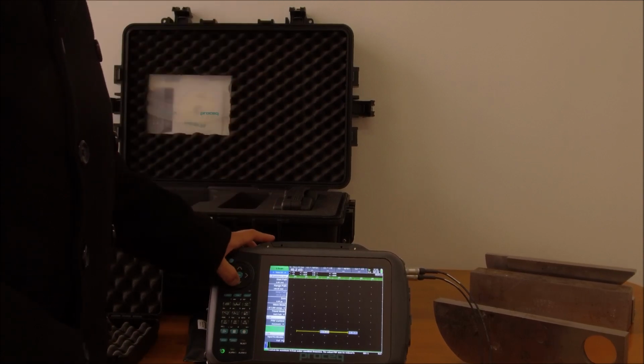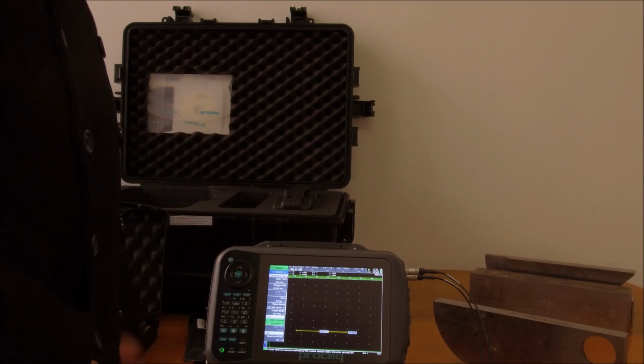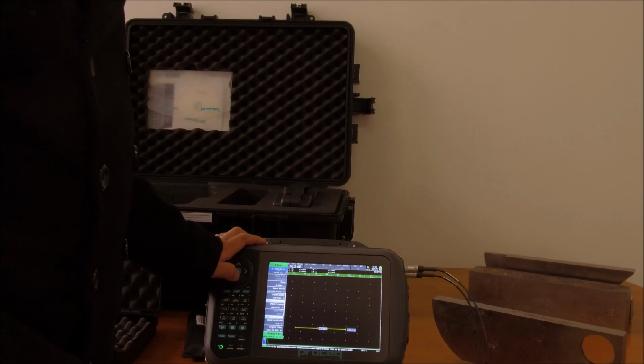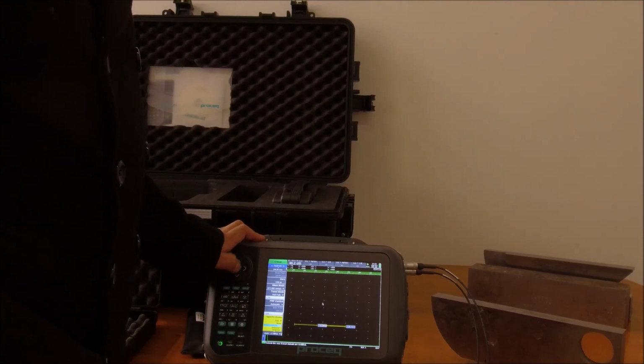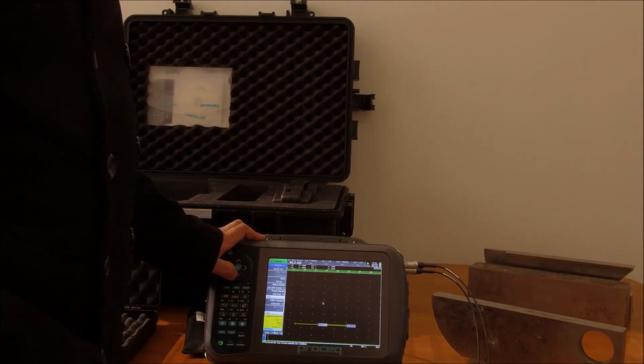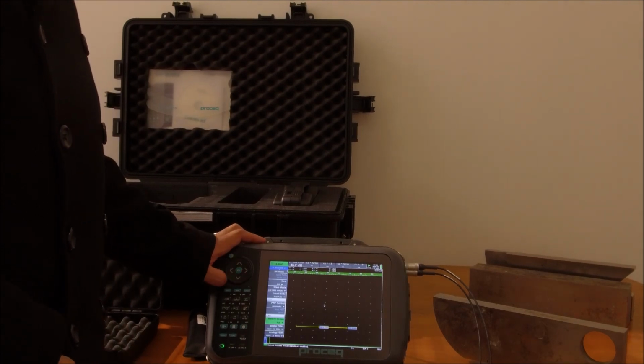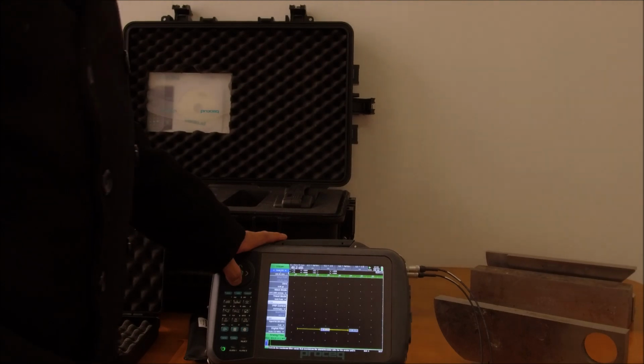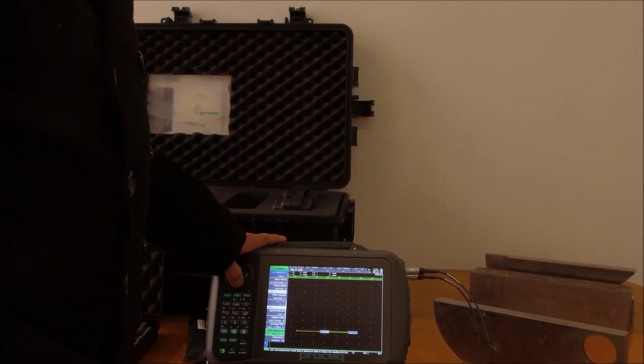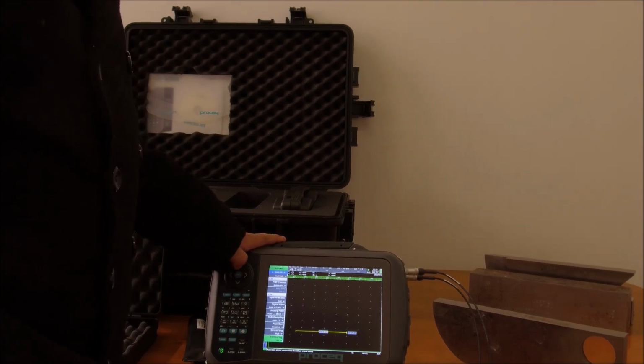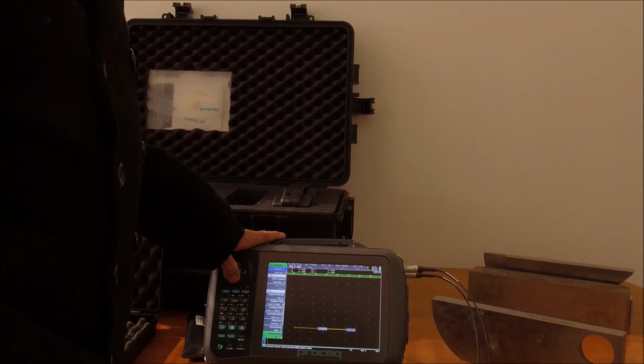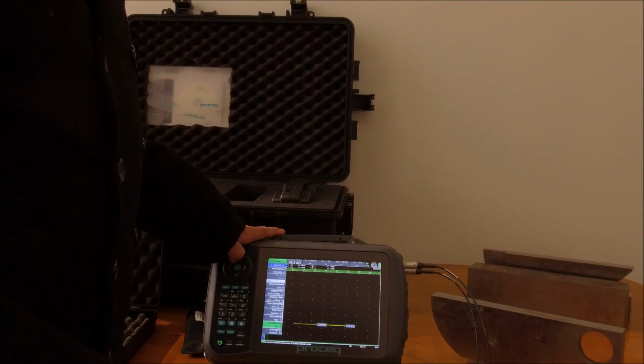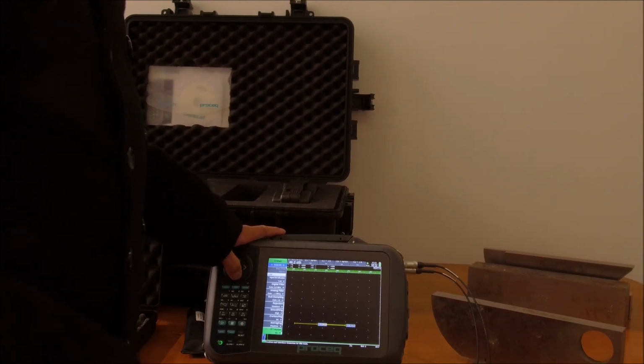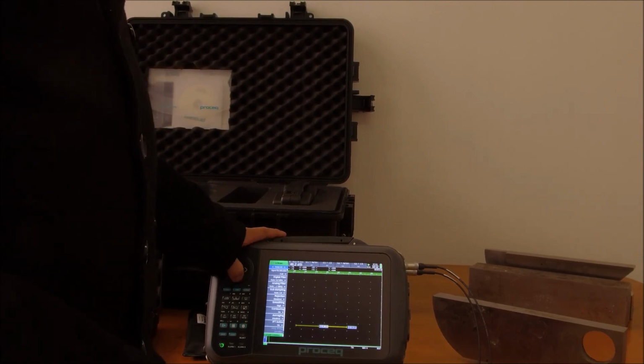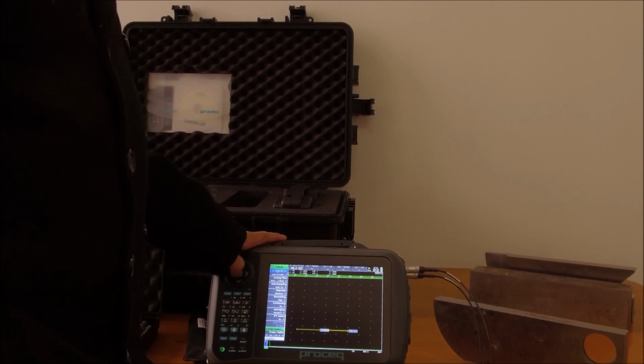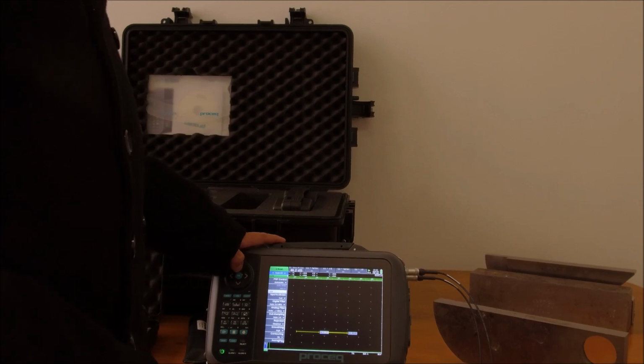PRF control, not something that we touch unless we know exactly what we're doing. If we leave it at automatic, it'll be tied to the range that we set. Rectification: whether we want it full, unipolar in the positive direction, unipolar in the negative direction, or no rectification whatsoever. In flaw detection, most of the time we're going to be looking at full rectification. We can set our filters, our sampling, our rejection. I'm sure at this point we all know that that rarely, if ever, gets turned on, and nor should it if we're testing to a standard. Smoothing, contouring, averaging, all of these things are software functions, and then we can change our probe connections as well if we wanted.